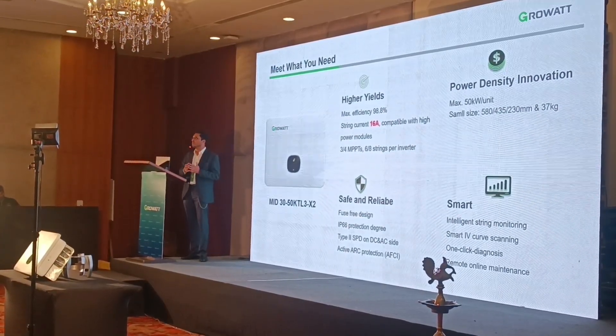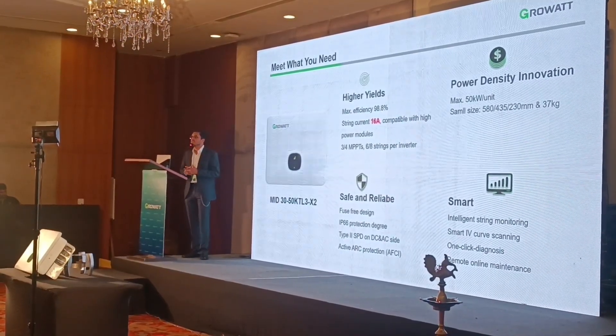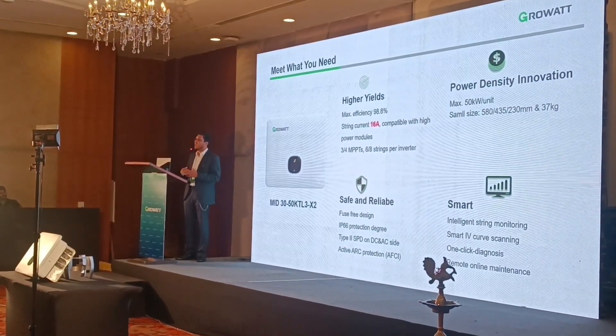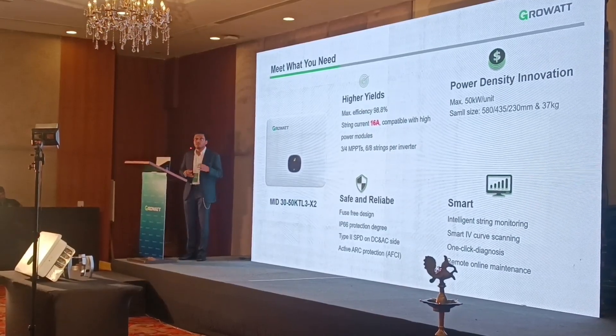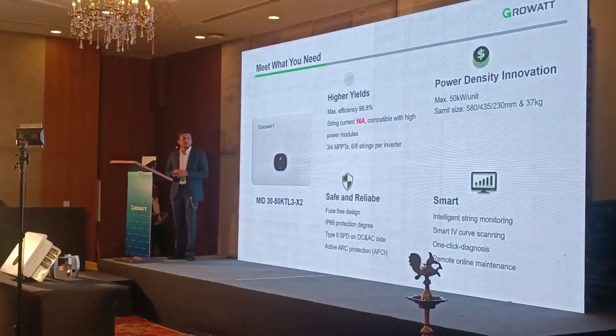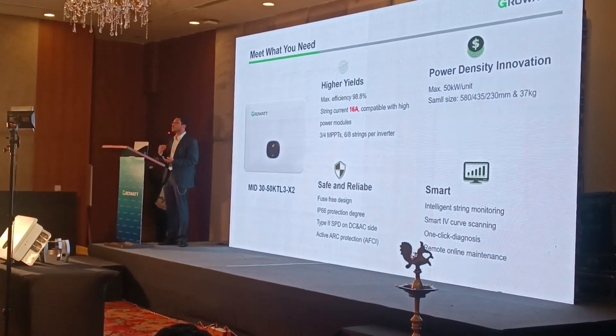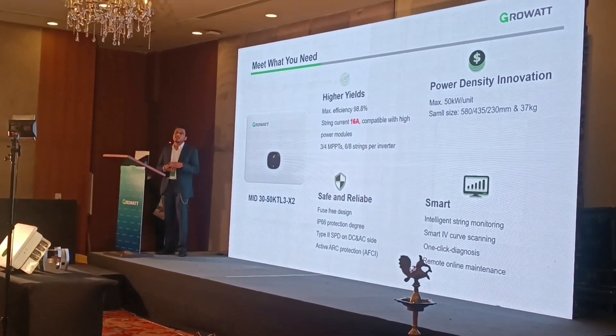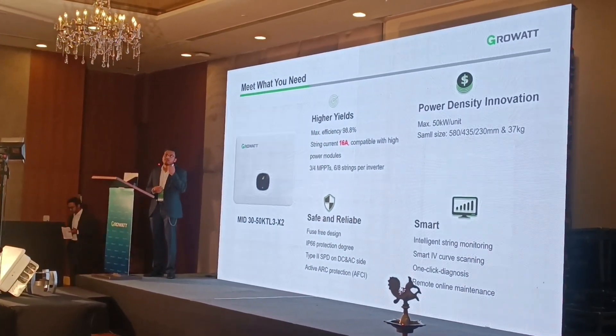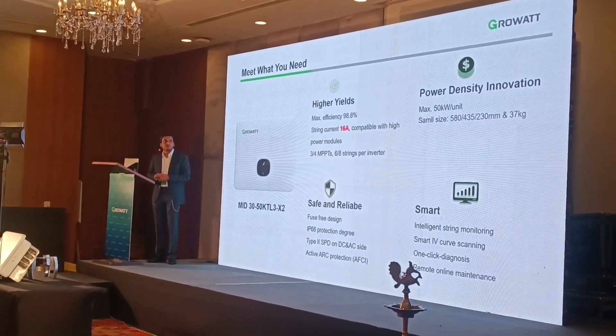Monofacial modules, bifacial modules, and high current modules are all coming with a current of 13 amperes and more. To cater to that market for C&I, we have come up with an inverter having a string current of 16 amperes. These options range from 30 kW onwards to a maximum of 50 kW, in two configurations: 30 kW and 36 kW come with three MPPTs, whereas 40 kW and 50 kW come with four MPPTs.